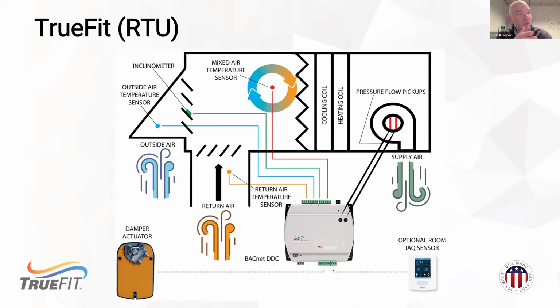The first would be a supply air measurement. This is a velocity pickup where we're taking a total supply. The second thing is temperature measurements for OA, return, and mixed air. So we see that we have all three of those temperature sensors, and that lets us calculate those mixed air equation numbers. We'll talk about why those are important in a second.